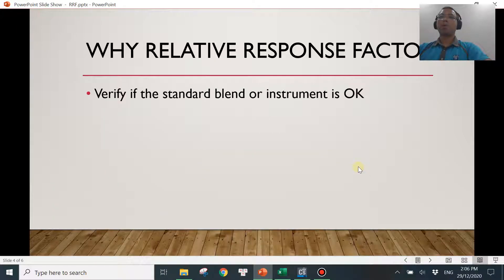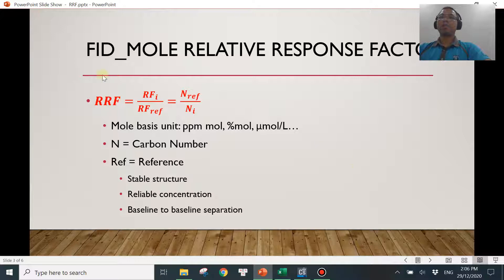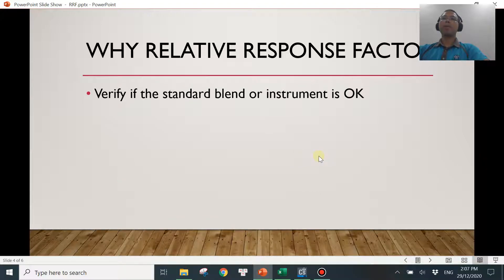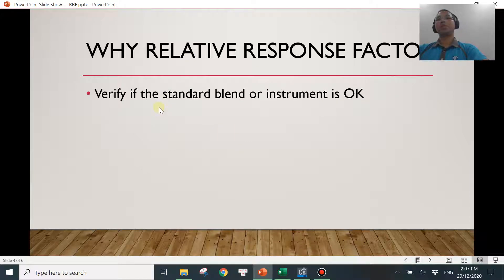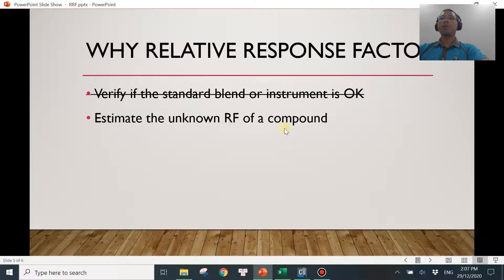Before we get into those two points, I need to remind you of this formula again — when it comes to molar FID, the relative response factor is defined as NREF divided by NI. In the last video, I was talking about how to use this relative response factor to verify whether the instrument or the standard is doing okay. In this video, I'm going to share two more very good points of using relative response factor.